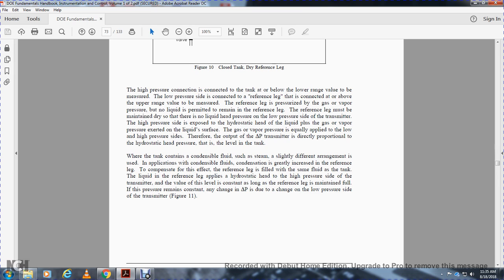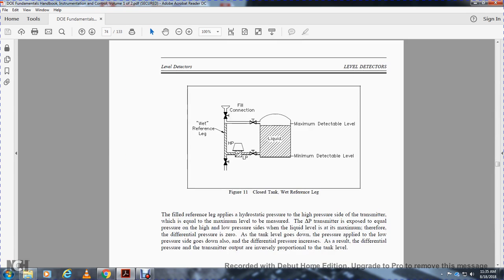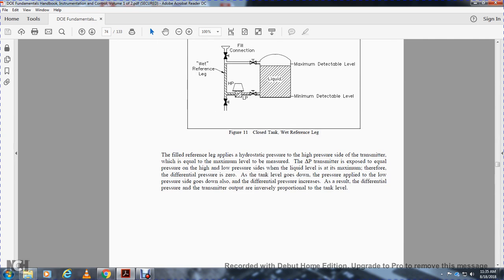If the pressure remains constant, any differential pressure is due to a change on the low pressure side of the transmitter. Figure 11 shows the closed tank with a wet reference leg with maximum detectable and minimum detectable level. The liquid fills the wet reference leg connection with high pressure and low pressure gates. The filled reference leg applies a hydrostatic pressure to the high pressure side of the transmitter equal to the maximum level to be measured. The differential pressure transmitter is exposed to equal pressures, high pressure and low pressure, when the liquid level is at maximum. Therefore, the differential pressure is 0.